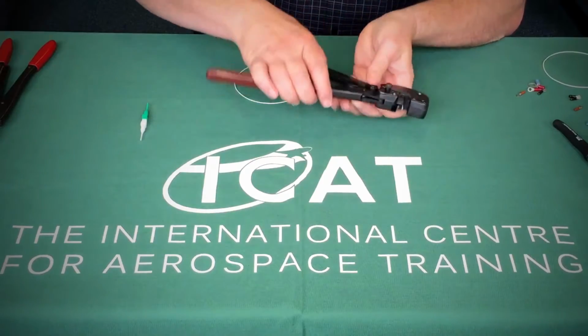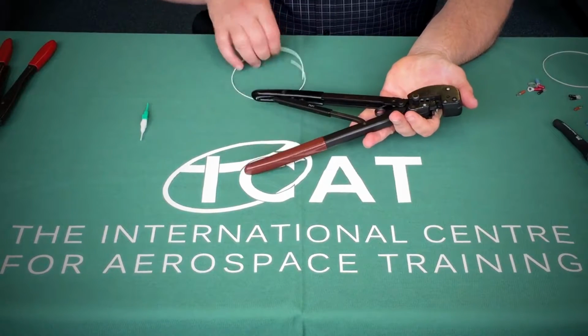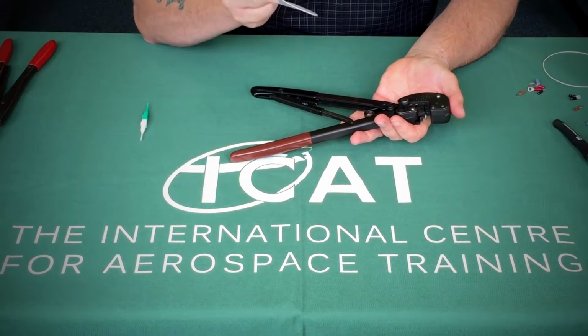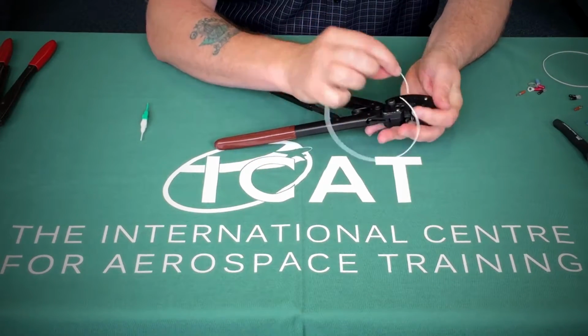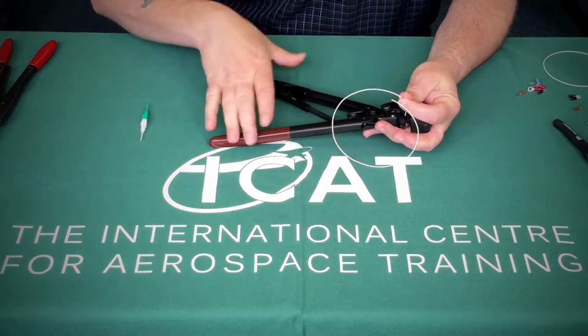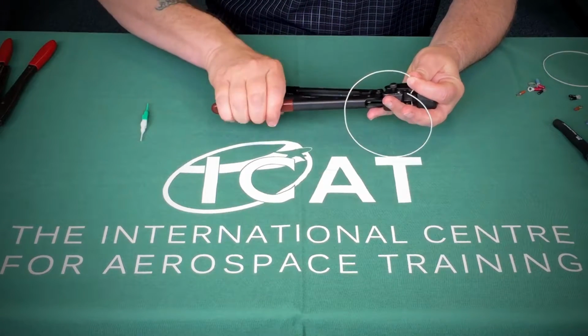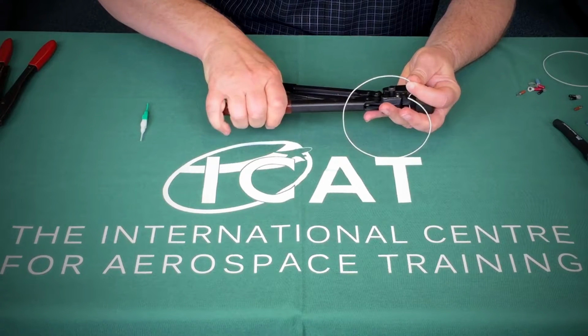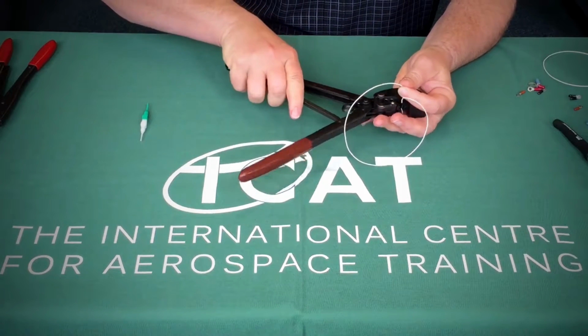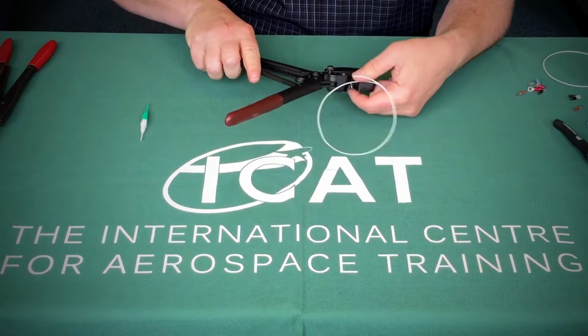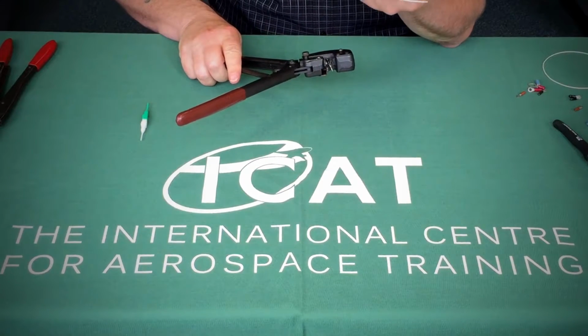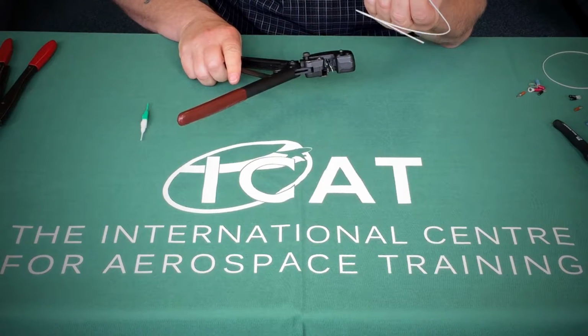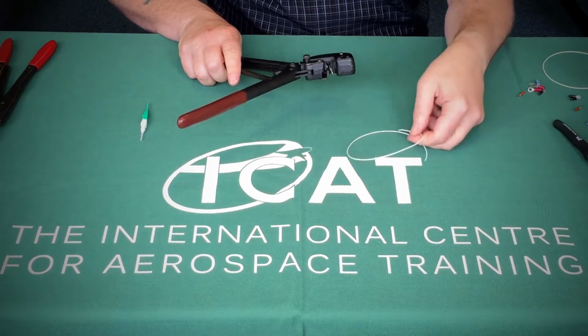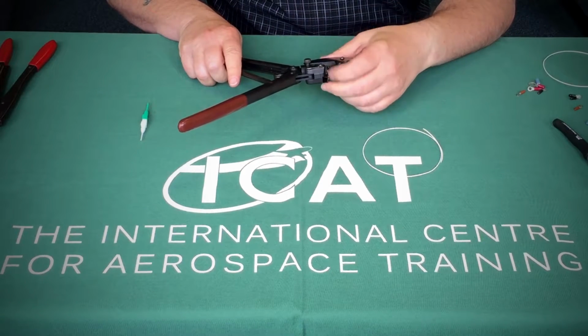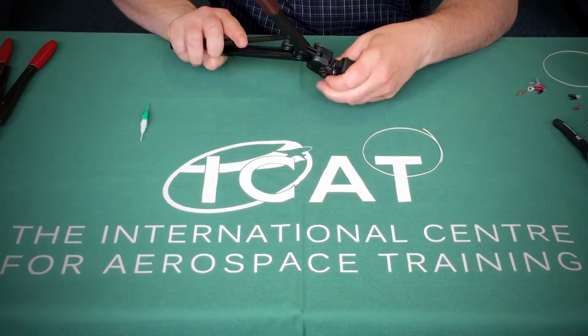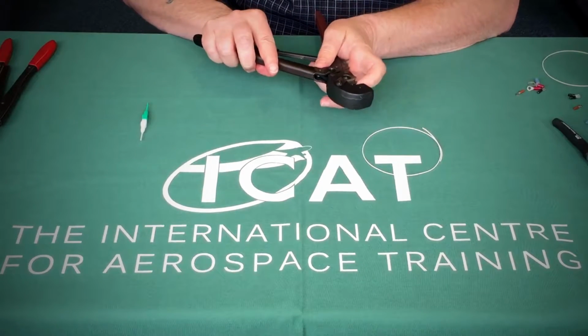Once I've done that, I can turn the tool over, and again, this time I've taken a piece of unstripped cable and I insert it into the back of the crimp itself. I then proceed to close the crimp up and complete the crimp when the ratchet opens. Now in this case, you can see that the cable has immediately fallen straight out of the crimp tool. That means that the insulation grip or pin is in the wrong position, and therefore I need to move it.